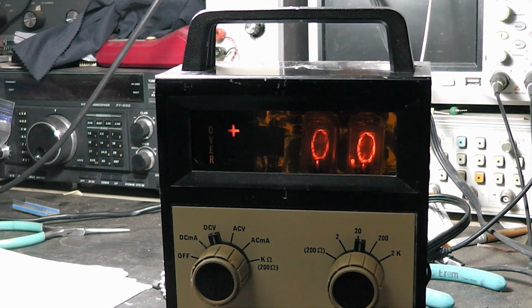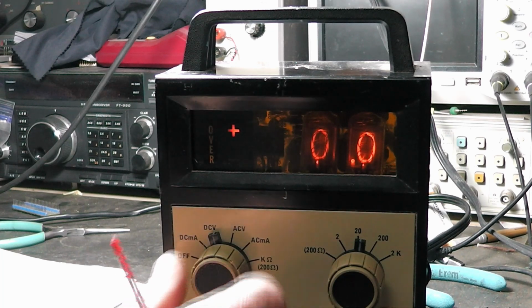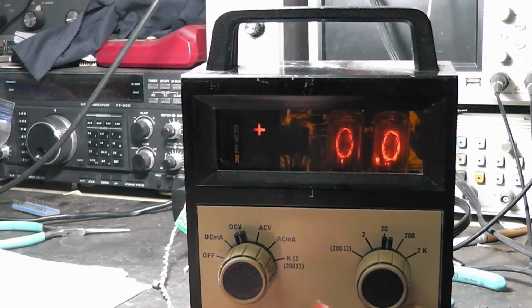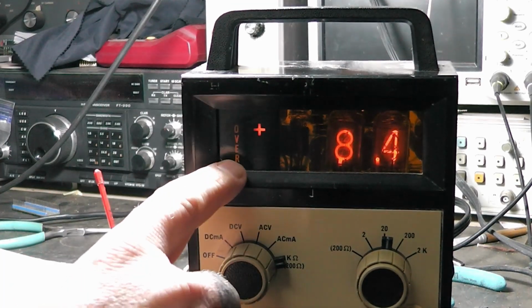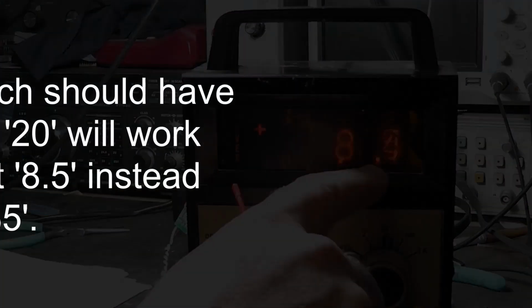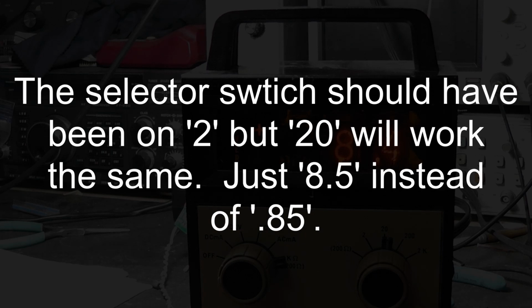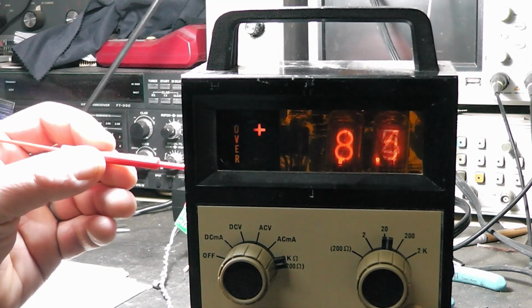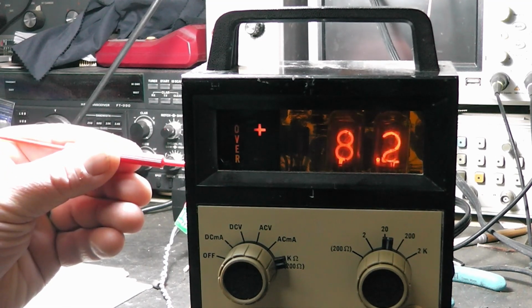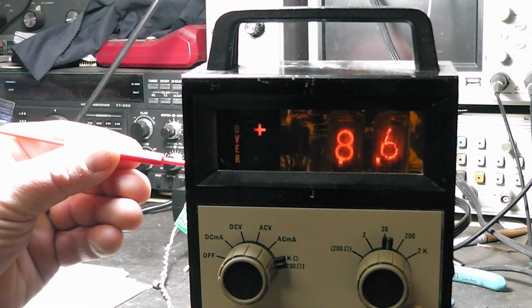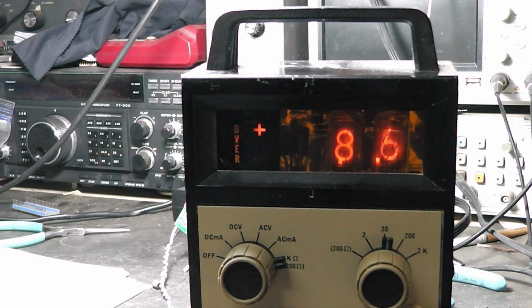Turn the function switch to the K ohms position and adjust the oscillator control for a readout of over 0.85. Okay, so what they're wanting you to do here, oscillator's right here on the side. I failed to mention that earlier, but that's the oscillator control right there. So if we move this over to here, we should have over and the 0.85. And that I've already adjusted at one point. And we can go in there, see if I go in there and test. See, that's wrong. And I'm adjusting that. So about right in there somewhere, because it says it can be plus or minus 0.15. So that's close.